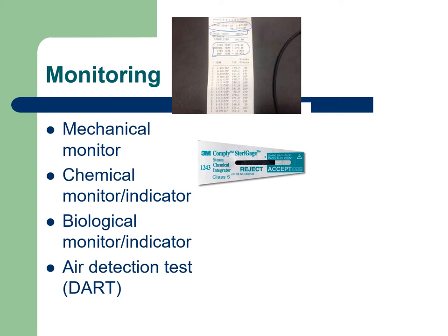If we were putting something into the gas sterilizer, the ethylene oxide sterilizer, or using some other method, there may be different types of integrators, ones specific for EO, or specific for peracetic acid or hydrogen peroxide. So you want to make sure that you get the right chemical integrator.